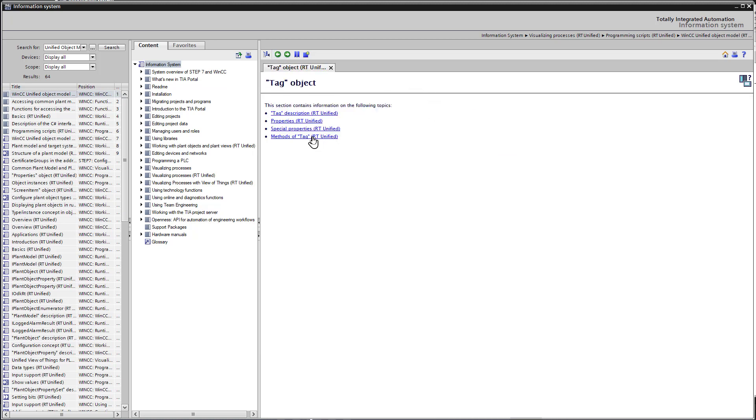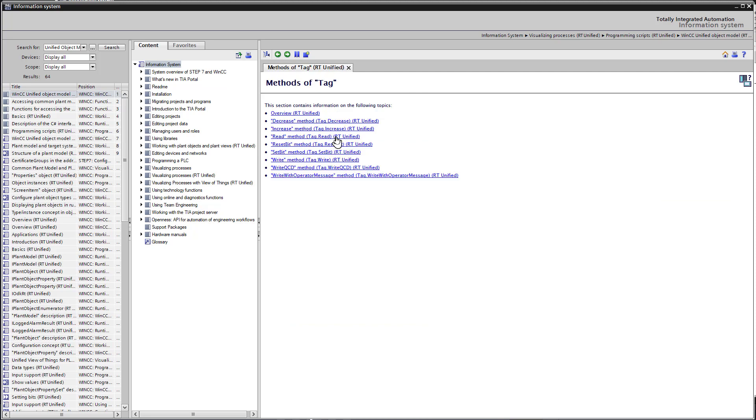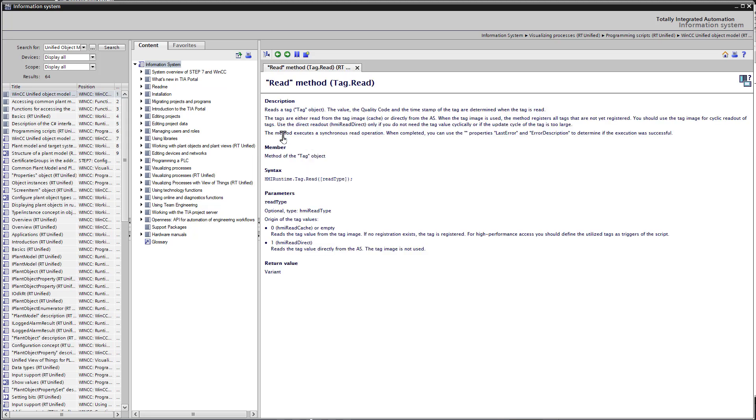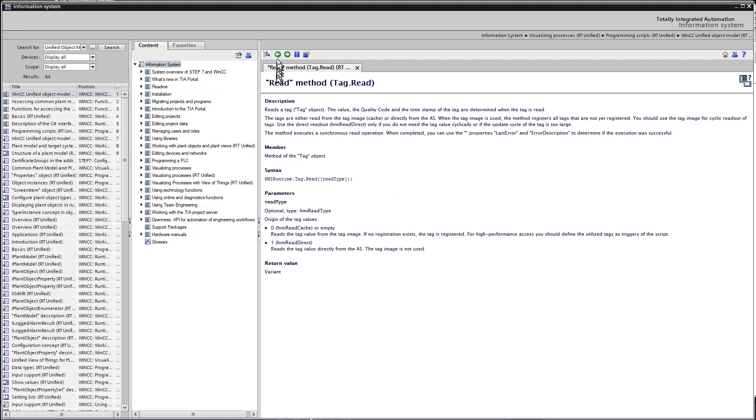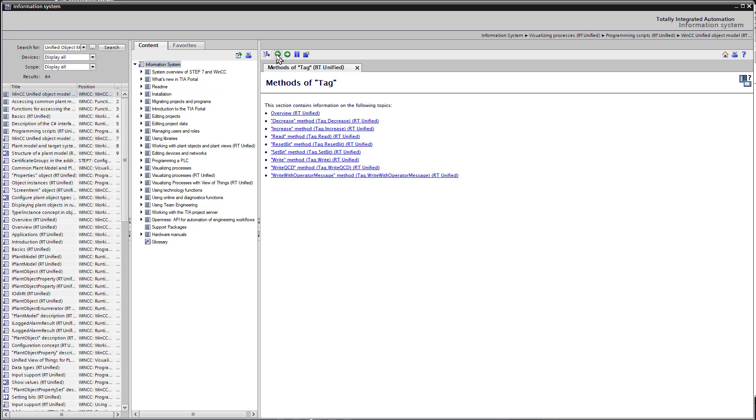If we look at the method, these are the things that we ask the tag to do, like read or write. So let's take a look at the read method. So at the read method, you can see that when you read, you can get the value, the quality code, and the timestamp. And you can read those properties and get the information. And it also takes an optional parameter called read type. And this is if you want to do synchronous or asynchronous. So for an internal tag, we're not even going to use this HMI read type. So there's a lot of good information in the help on the object model. So if you're working with different objects, it's a good idea to come back and review that. And you can see how to use these objects and methods.